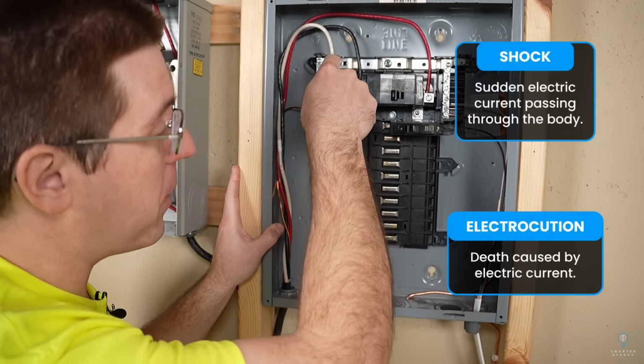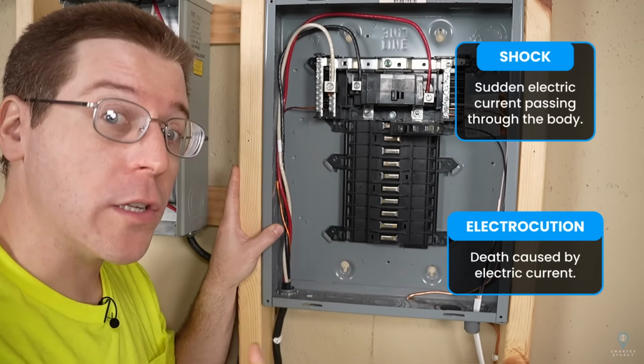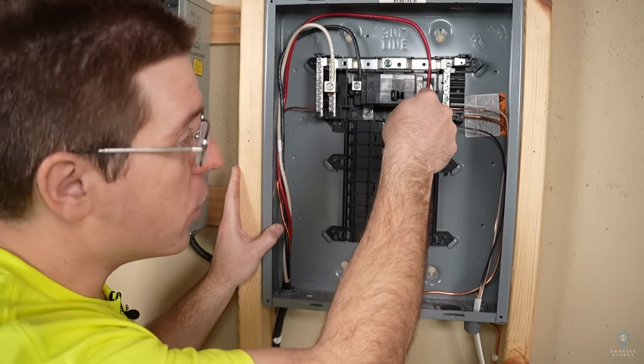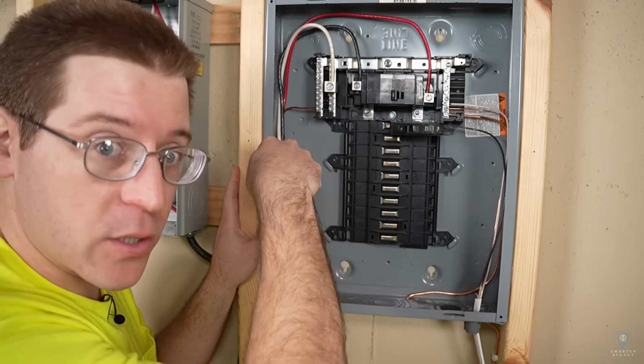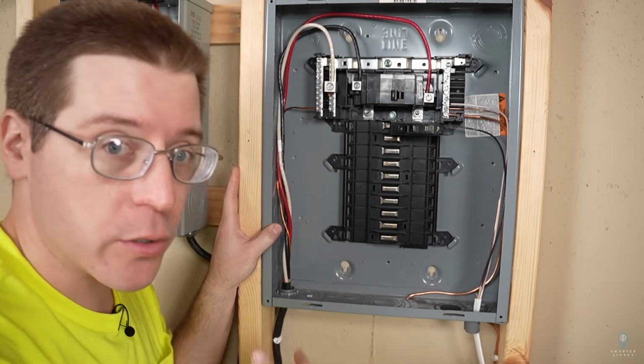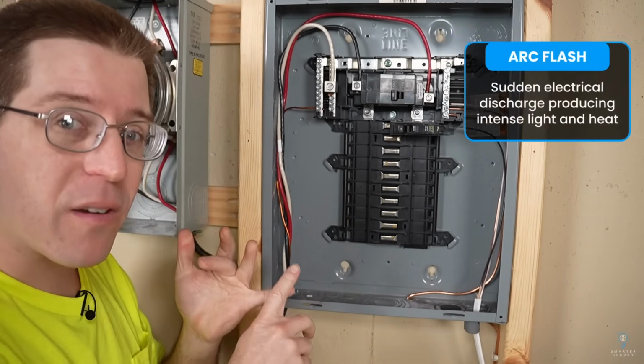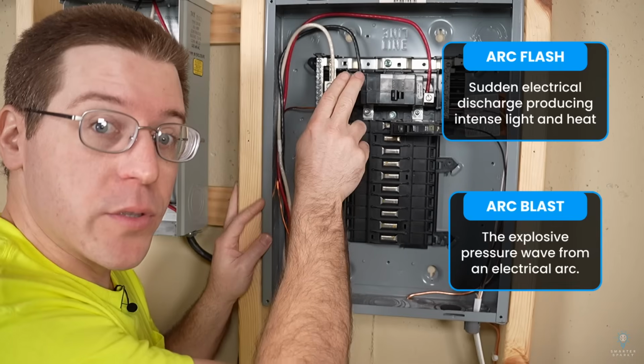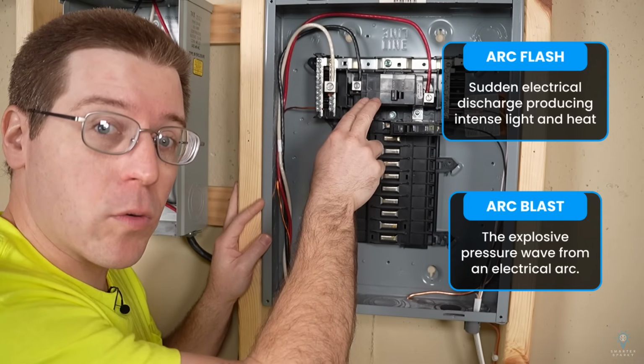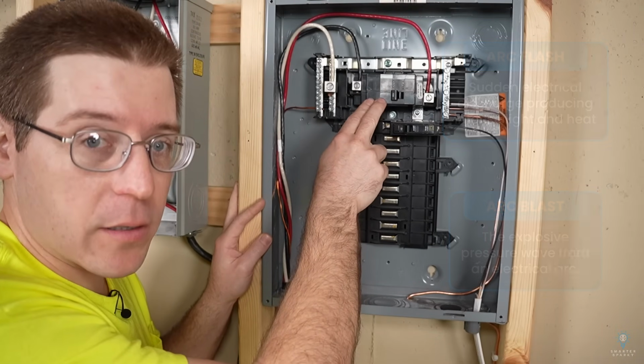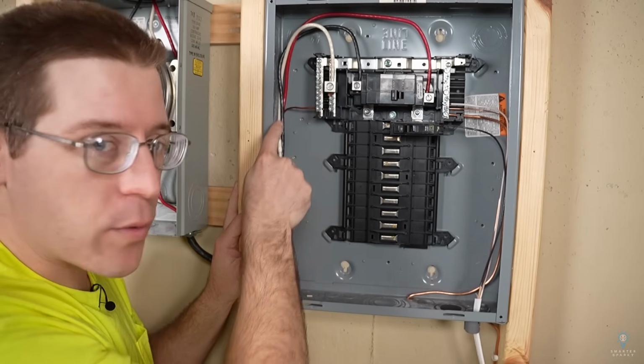Furthermore, if you were to drop a screwdriver, a wrench, or a screw across those lugs, or from those lugs to the panel, or from those lugs to the neutral bar, that could result in an arc flash or an arc blast. So the main circuit breaker only interrupts the lines or the hot conductors. The neutral always remains connected.